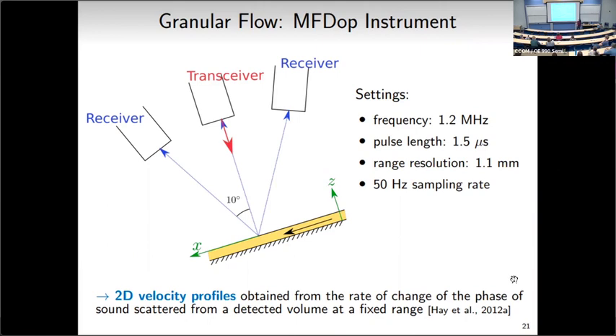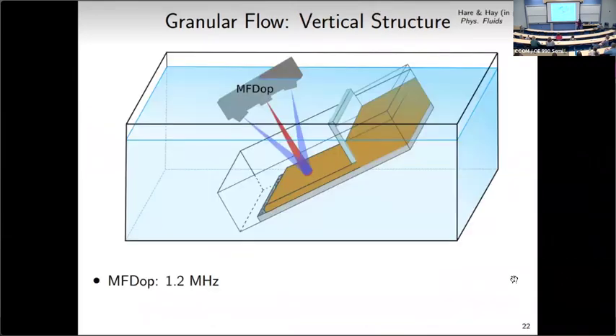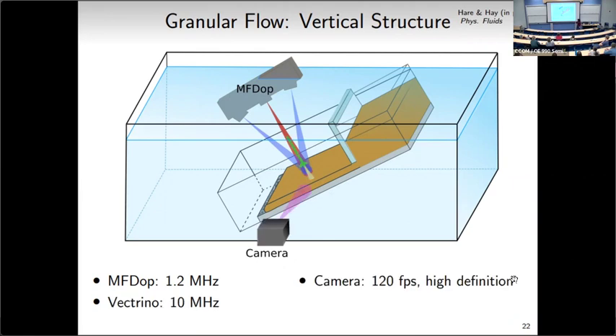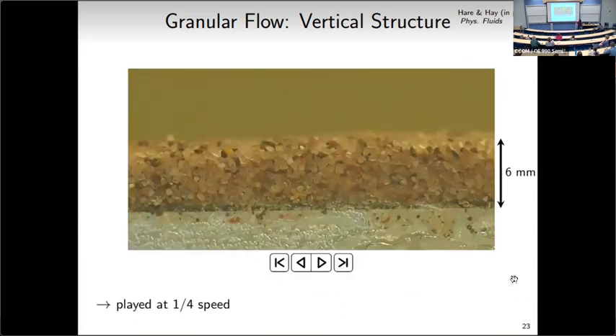Using the MF-Dop, we can obtain 2D velocity profiles from the rate of change of the phase of sound scattered from a detected volume at a fixed range. So back to our setup drawing. Here's our MF-Dop. We're going to get a velocity profile through the moving layer, downslope from the gate again, and away from the chute sidewalls at 1.2 megahertz. And I'm going to compare that velocity profile to one obtained by the Vectrino, the off-the-shelf acoustic instrument you can buy, at 10 megahertz. And then a camera looks through the chute sidewall. It's the same camera, so 120 frames a second and high definition.